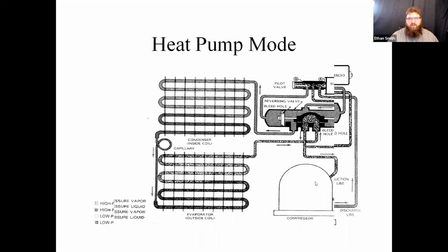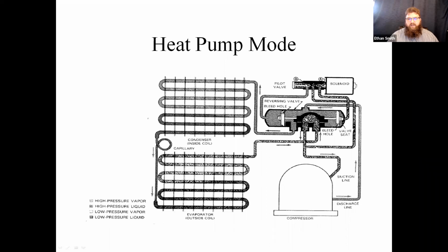In the heating mode, we're going to move that little clamshell over, and that way it's going to collect refrigerant off of the outdoor coil line and put that into the suction line. Now, the way these things move over is there's a little solenoid up here on what's called a pilot valve. The solenoid doesn't actually directly control the clamshell in the reversing valve. We could make a solenoid valve that would control that. It'd weigh about 10 pounds. It'd be 240 volt coils and just be super expensive.